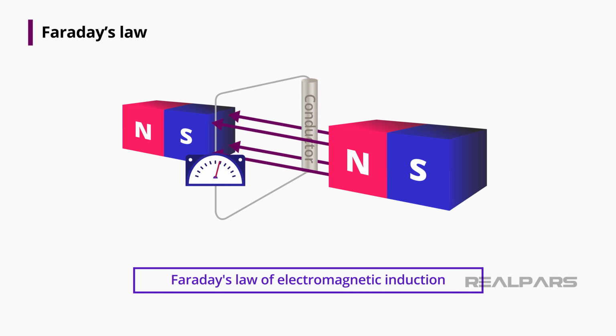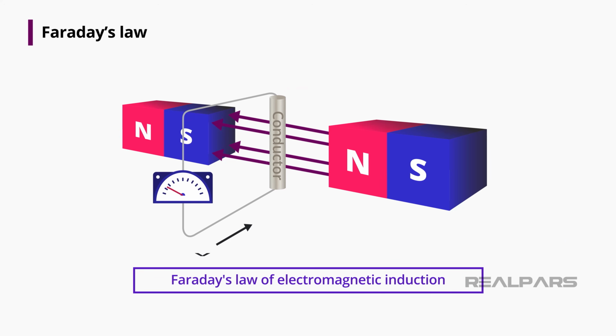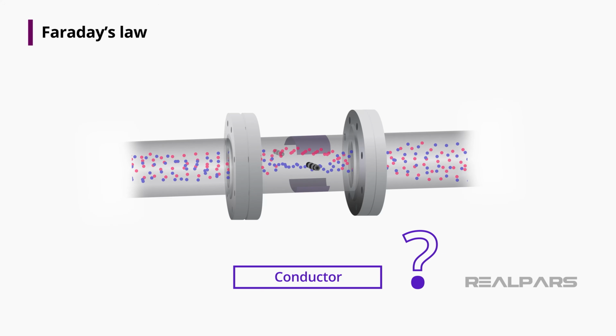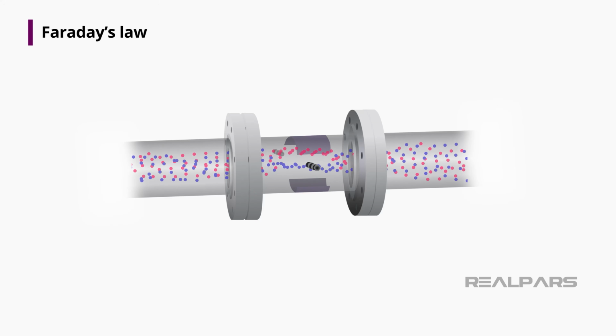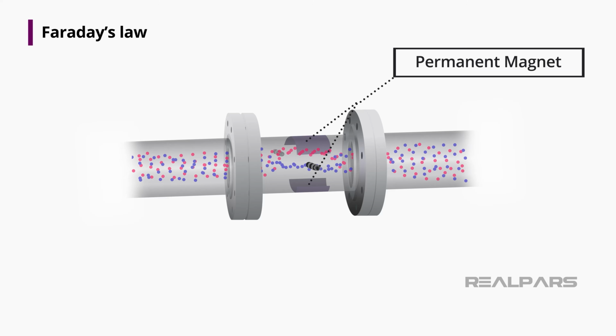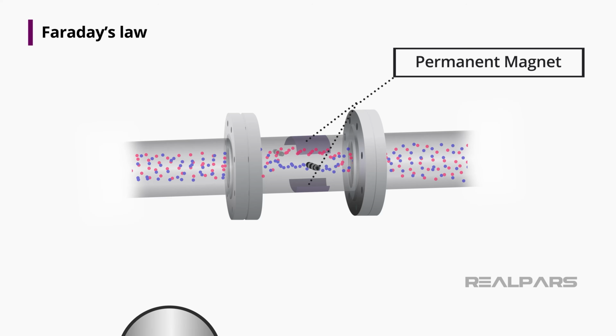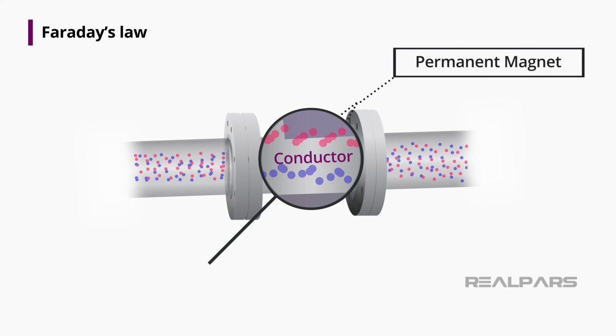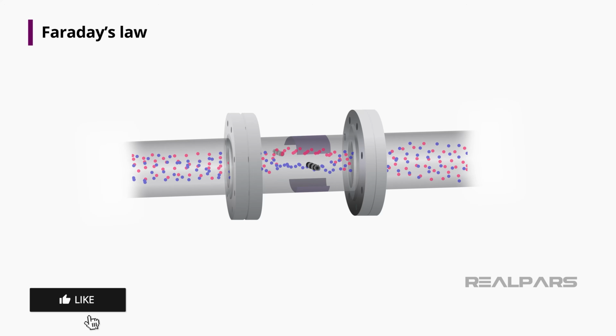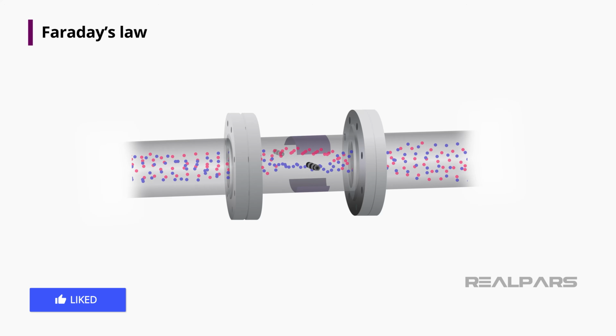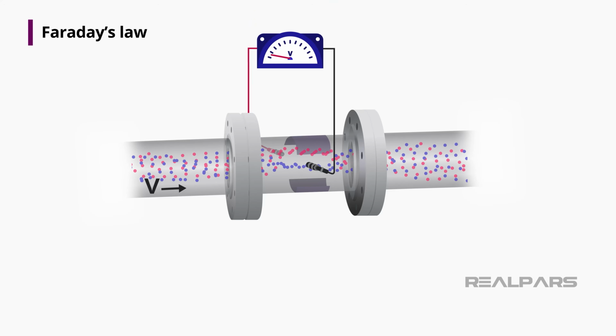To generate a voltage according to Faraday's law, we must have a moving conductor. What is the conductor in our flow application? I had mentioned that our mag meter has a stationary permanent magnet, so the conductor must be the flowing fluid. And indeed, it is. And as the flowing fluid passes through the magnetic field at right angles, according to Faraday's law, a voltage must be developed that is proportional to the fluid velocity.